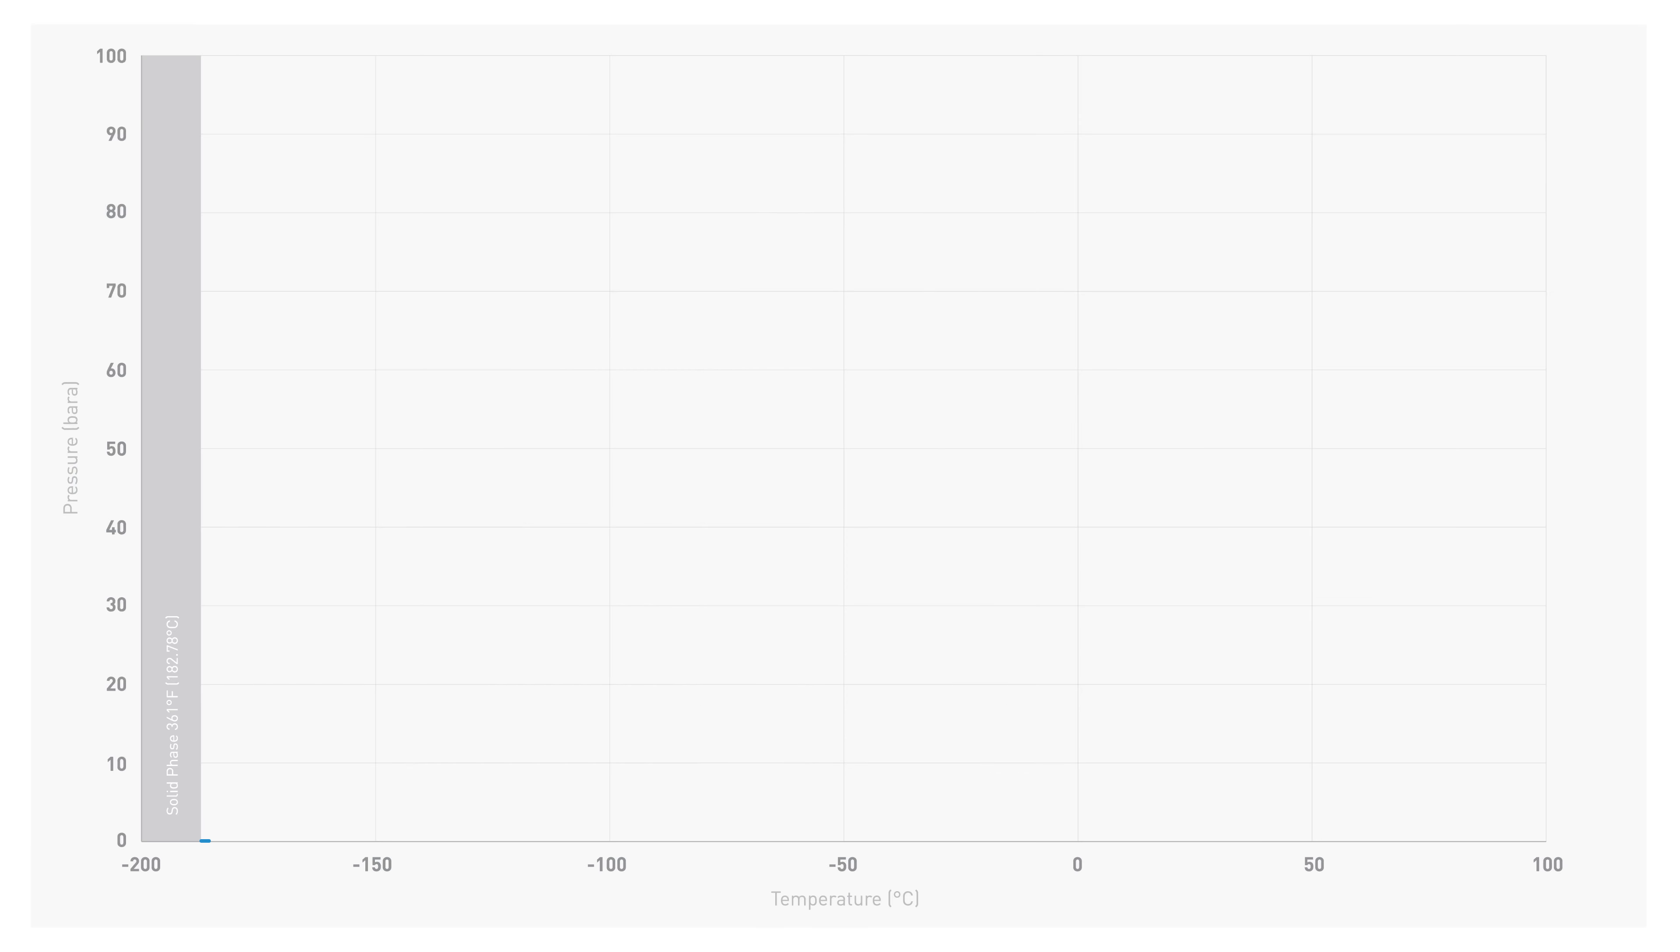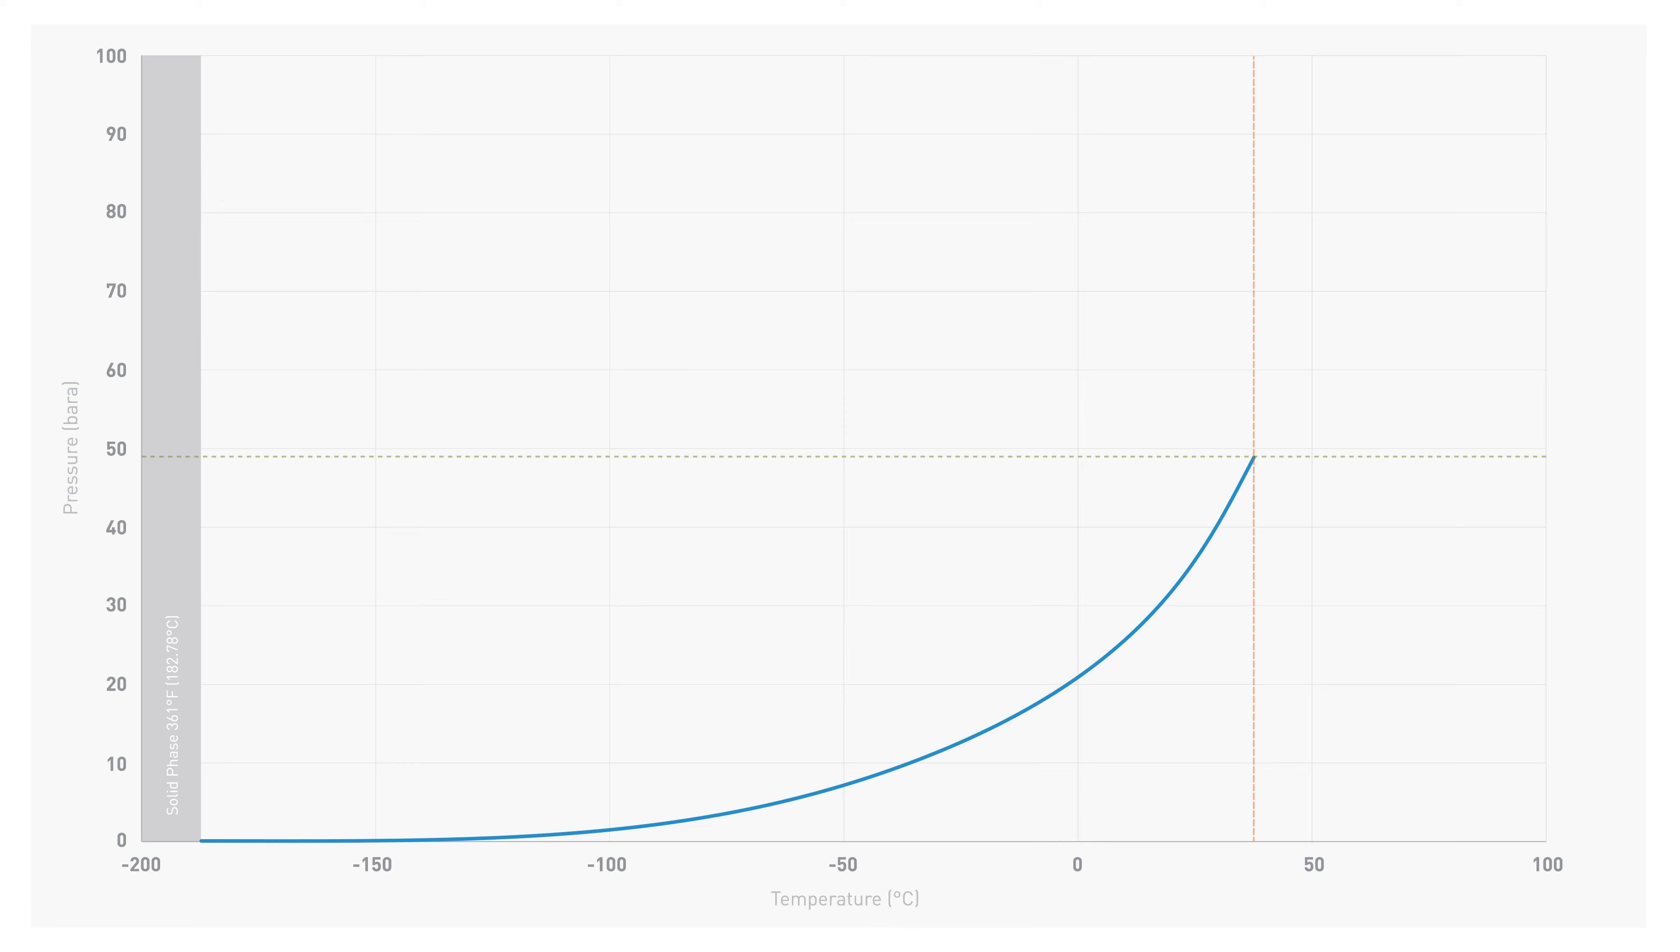In conventional contacting wet seals, the inboard seal faces are surrounded by liquid ethane. The liquid ethane lubricates the seal faces and must remain in its liquid phase to be effective.